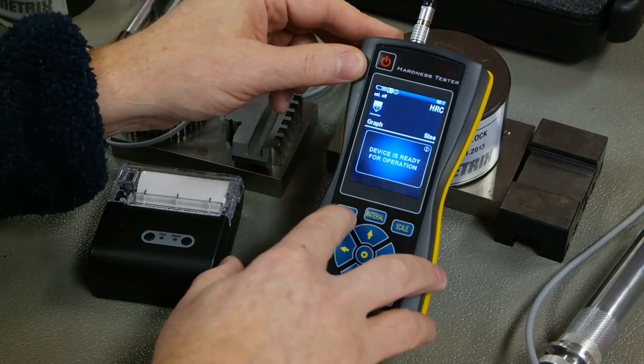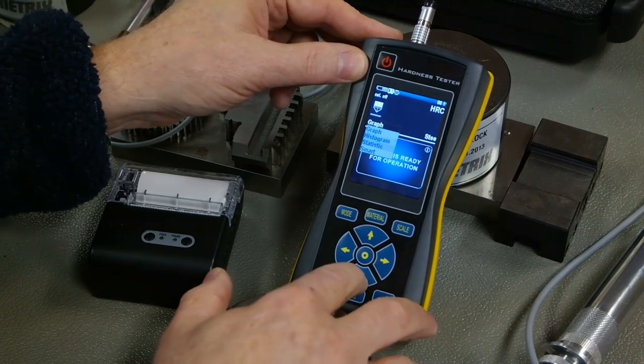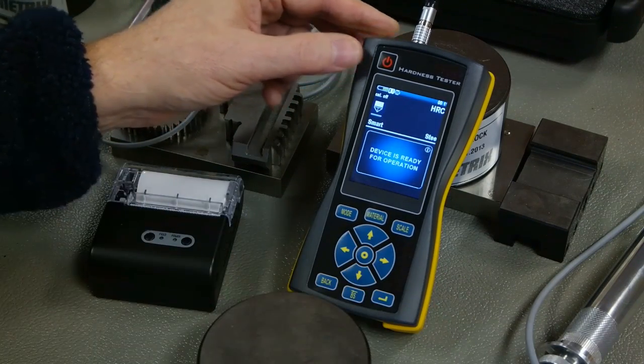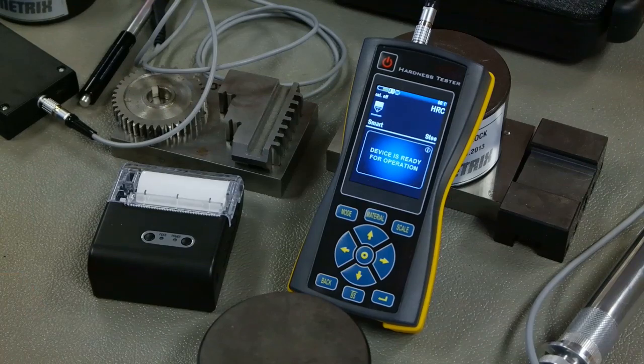And if I go now into smart mode, what smart does is it will read 3 tests, and if any of those tests are varying by the tolerance I can specify in the unit, it will automatically delete those. So if you do an erroneous test, it will automatically dump it. So I'll show you how this works.